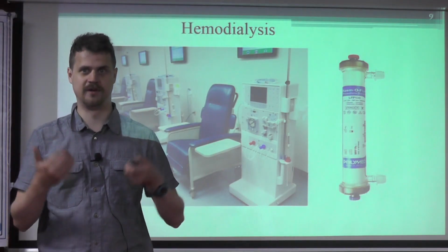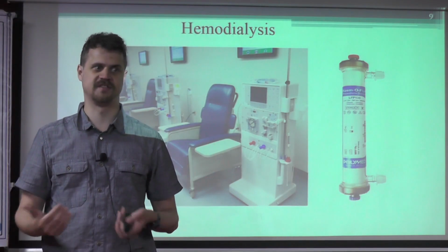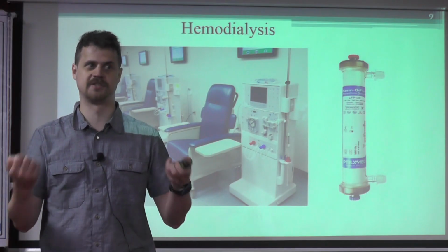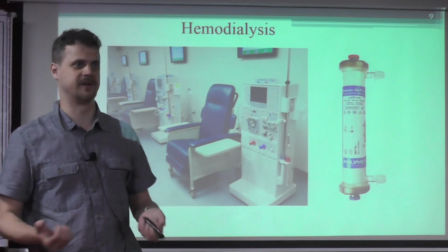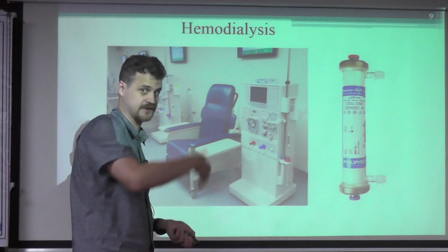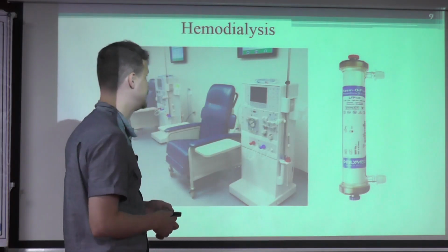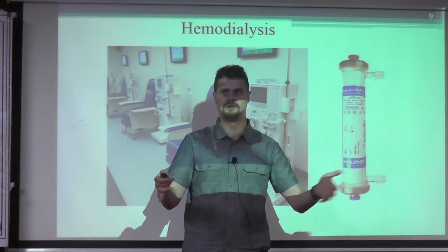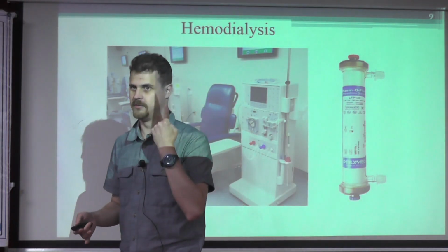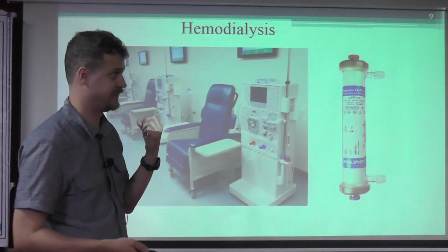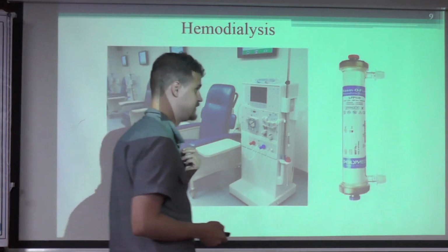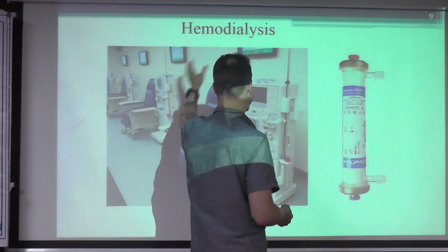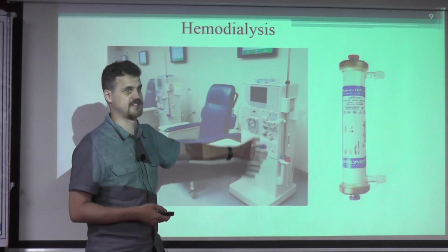That means that the usage of reverse osmosis is like the main requirement to make sure that there will be no microorganisms presented in the water used for the dialysis solution. So basically, it's a method that requires a huge amount of water for only one patient, which makes this method quite expensive, and this system are usually stationary.